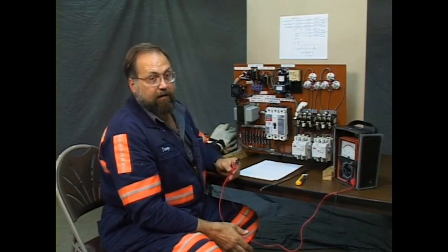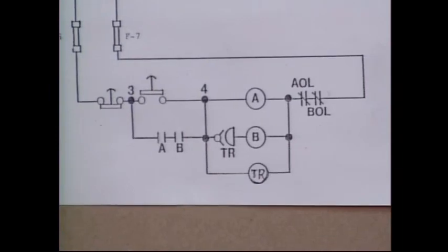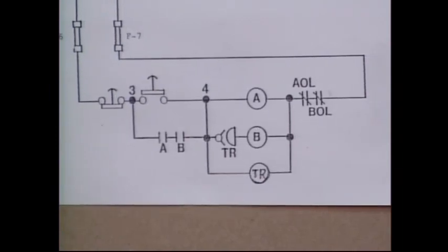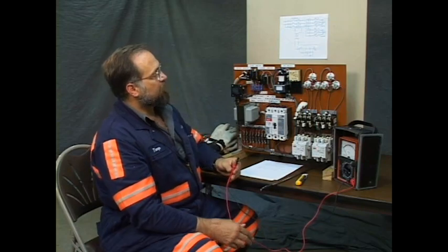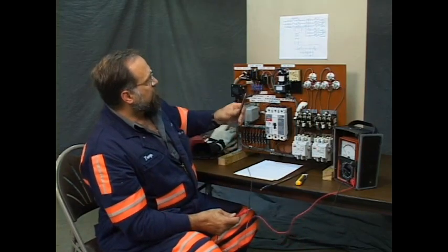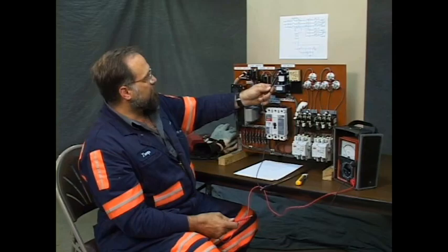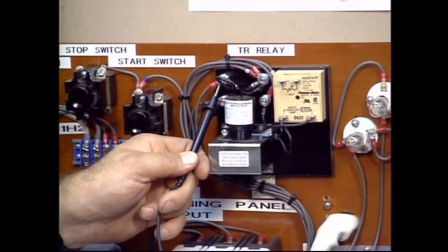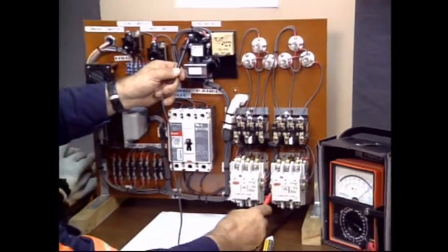It's not necessarily how things lie or the order they lie in on a machine or how close they are in proximity to each other. That illustrates how it's connected. And as a matter of fact, this TR mercury tube was quite far from the B coil. It's all the way down here. Let's read that. Yeah, it reads good.